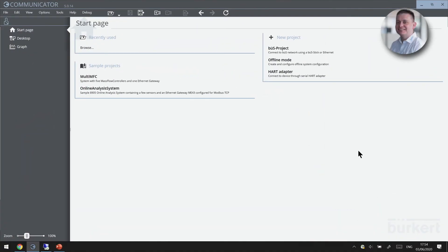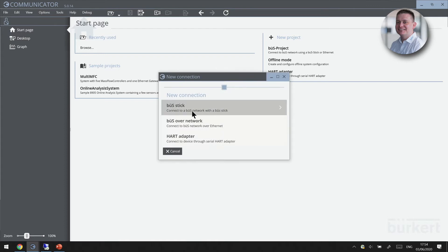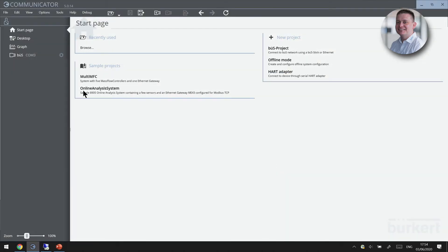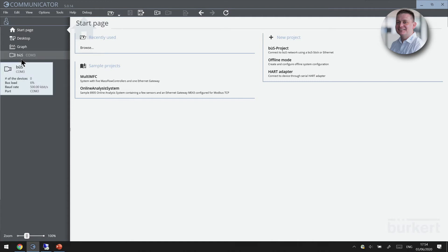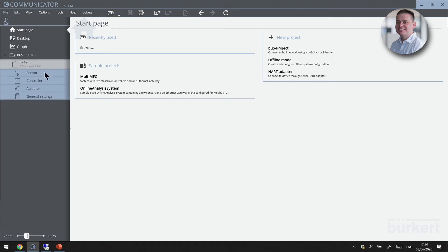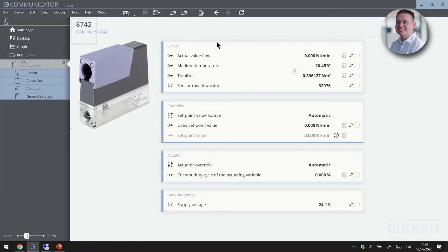Let's take a look at the Bürkert 8742 Mass Flow Controller. Let's establish a connection in our communicator software by using the bus stick USB connection. Our device will show up on the product tree on the left-hand side and we can expand its features by clicking the plus button. When we click on the device itself, we are presented with a host of values such as flow rate, temperature and totalizer.